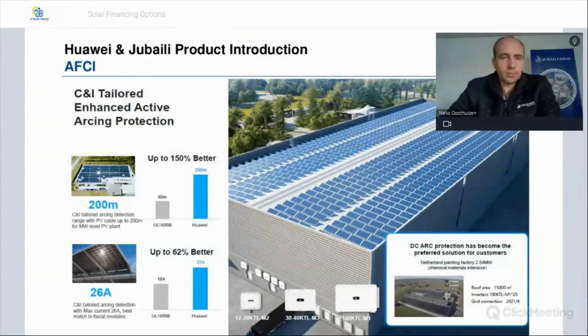With the AFCI feature built in, if the inverter detects a fault, it will immediately shut down. I think it's less than 1 second. The inverter will shut down to protect itself, and it will also give you an indication of where the fault is. On the bigger inverters, 100 kTL and 200 kTL, it will specify which string it is. If it's a smaller inverter, the 30 to 40 kTL M3, and you have used optimizers, it can even pinpoint the exact module where there might be a problem with arcing.